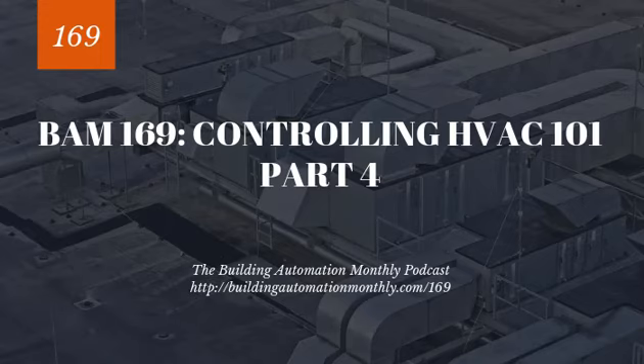Now we come into this thing called steam. Now, steam is really bad, and it's really good at the same time. I've seen invisible steam leaks cut through broomsticks. I mean, that's one of the things you do as you're walking around trying to figure out, oh man, is there a steam leak? You walk around with a broom and you can swipe it and steam will cut through that. I've seen people get burnt on their hand just getting close to an uninsulated steam pipe. Steam can really hurt you.